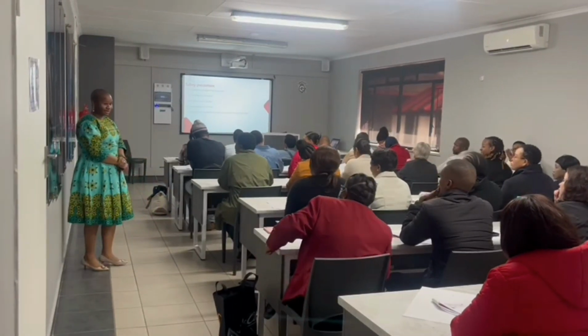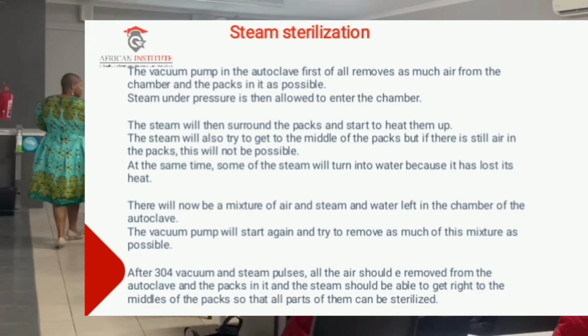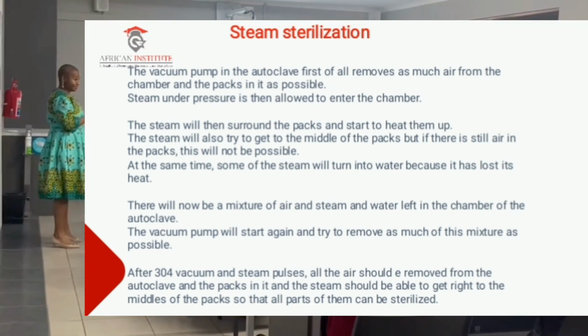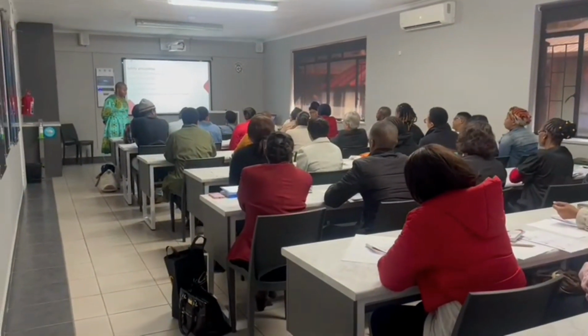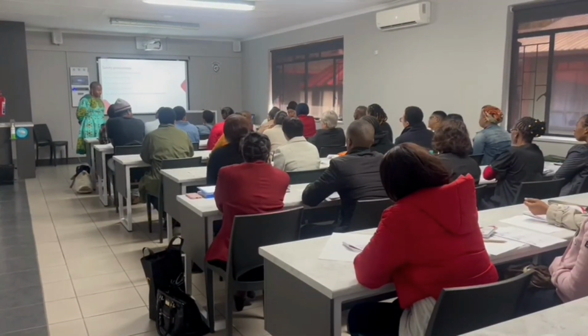At the same time, some of the steam will turn into water because it has lost its heat. There will now be a mixture of air and steam and water left in the chamber of the autoclave. The vacuum pump will start again and try to remove as much of the mixture as possible. After 3 or 4 vacuum and steam pulses, all the air should be removed from the autoclave and the packs in it, and the steam should be able to get right to the middle of the packs so that all parts of them can be sterilized and be sterile.